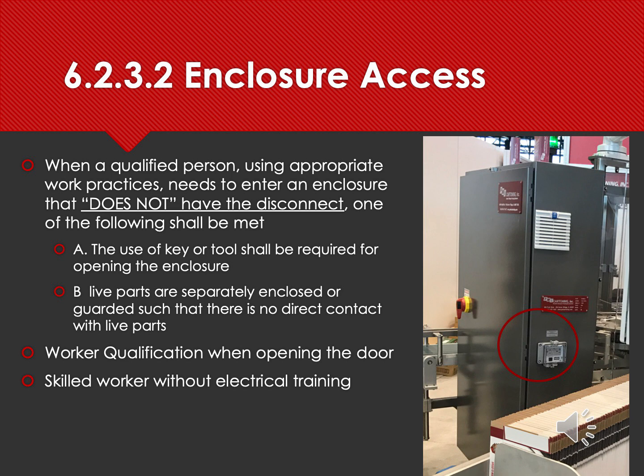So this slide talks about the enclosure access as it's defined in NFPA 79. Most facility maintenance workers, both qualified and skilled workers, perform fine tune-ups on their machinery to optimize the process parameters, right? With just accessing the control panel. What if the enclosure doesn't have a disconnecting means? Well, they need to meet one of the criteria outlined below, okay? The use of a key or tool shall be required to open the enclosure. So if you meet this requirement, you can open the panel access without this disconnecting means. Next question is, will an access to just a key or a tool make a person qualified enough with electrical work? Okay, let's look at the second one.